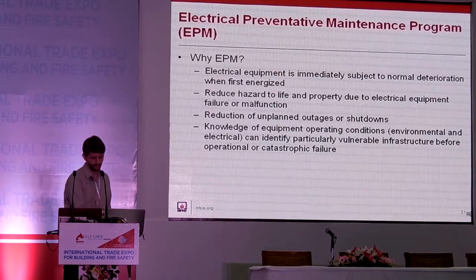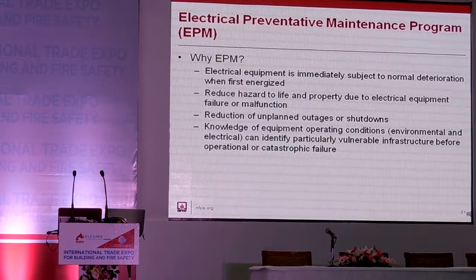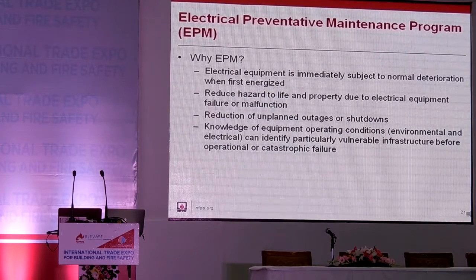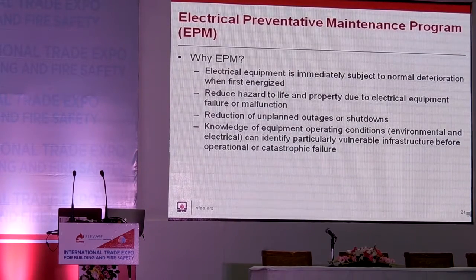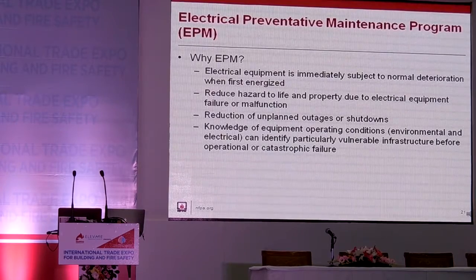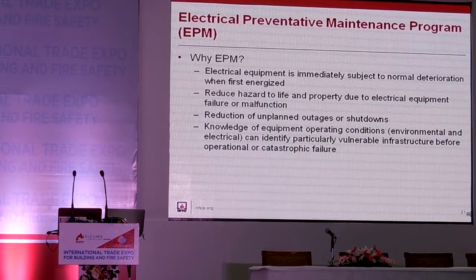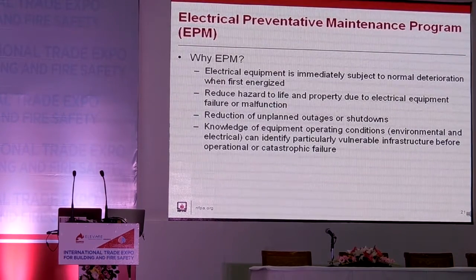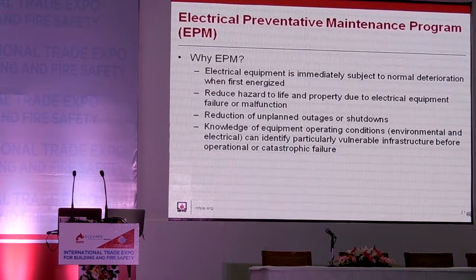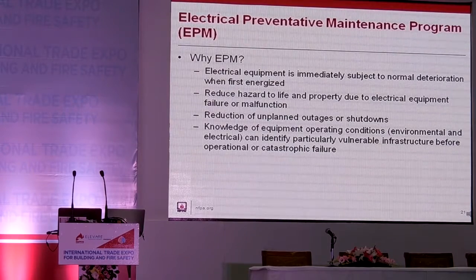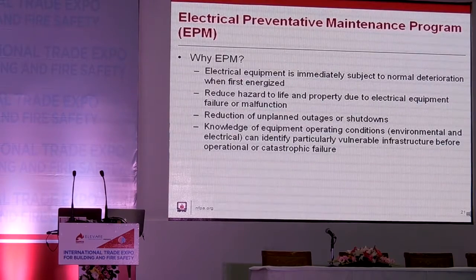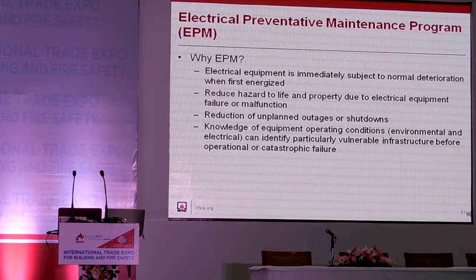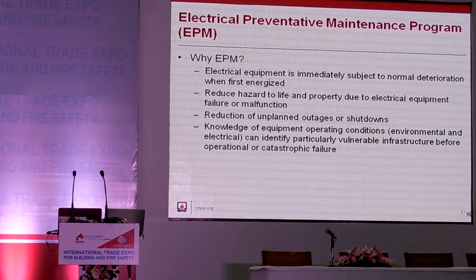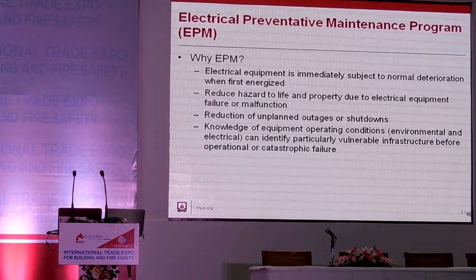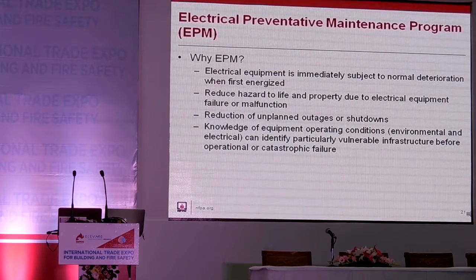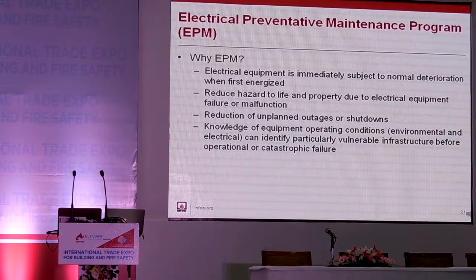Let's take a look at some of the reasons why an electrical preventive maintenance program makes good sense. First, electrical equipment is immediately subject to normal deterioration when it's first energized. Now, electrical equipment differs depending upon the type of equipment. Equipment such as motors, motor starters, and other devices where the contacts open or close frequently, or where there's rotating equipment, are subject to higher degrees of deterioration than equipment such as a panel board that's relatively static and typically is not subject to severe operating conditions.